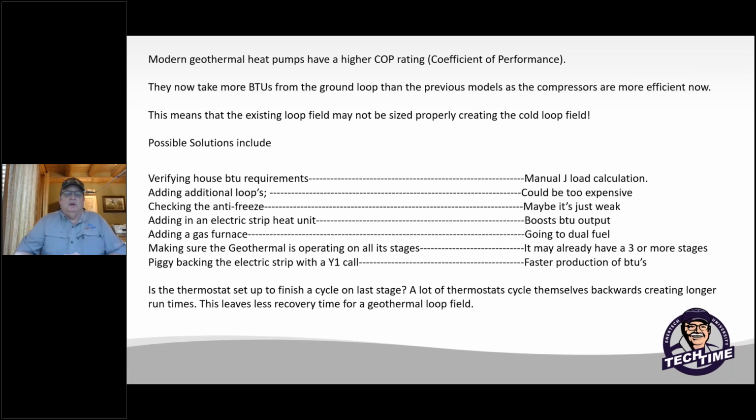So there are some solutions, especially when you're doing a retrofit or coming back in to repair this water condensation. Always remember that one of the most important things is a Manual J load calculation, or some type of heat loss calculation on the home, to really determine whether this heat pump is going to be able to handle it.